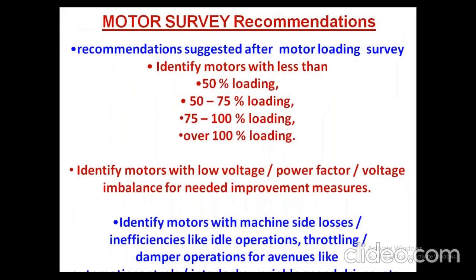Coming to the motor survey recommendations, basically any motor running around 50 to 75% is fine. Any motor above 100%, the motor either needs to be replaced or the load has to be optimized. The load has to be looked into. Many of our auditors think the motor is a problem. Motor is not a problem.